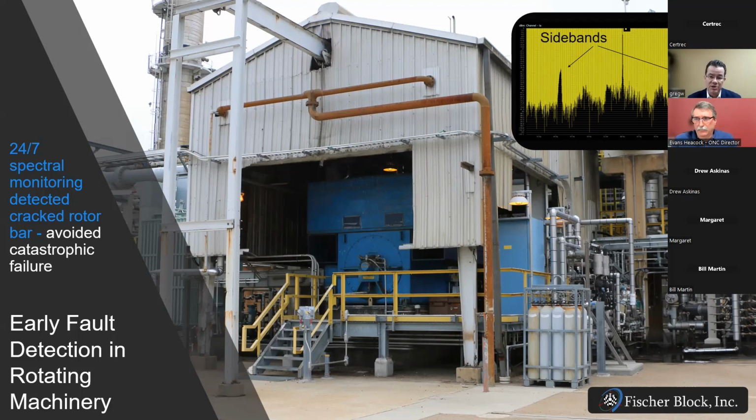characteristics. And what's important here as well is the noise floor, because as those sidebands start growing, the lower the noise floor, which is really the dynamic range of the monitoring system, the earlier our software can start tracking these sidebands that are growing in height, and they grow over weeks and months. And so the lower the noise floor, the more time the maintenance group has to plan for an ultimate inspection or a repair. And so we trend that over time, and extrapolating that trend line, they can see, okay, in 6 months we need to be in there to do an inspection. So it's very much supporting a proactive maintenance process. And in this case, they found cracked rotor bars when they went in there.